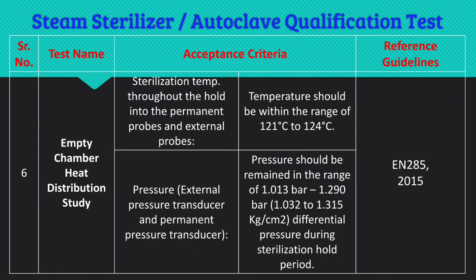For the empty chamber heat distribution study, there are several acceptance criteria to monitor. The sterilization temperature throughout the hold, measured via permanent probes and external probes, should be within the range of 121°C to 124°C — that is, a +3°C band from 121°C — as given in EN 285:2015.